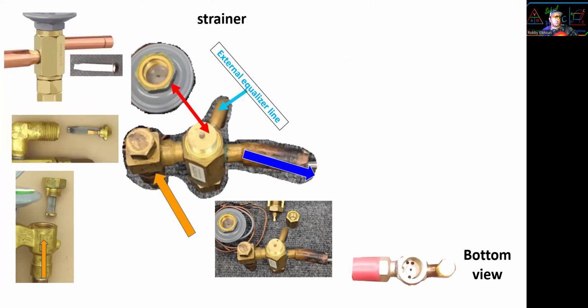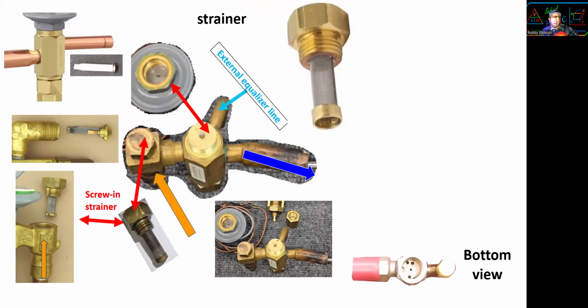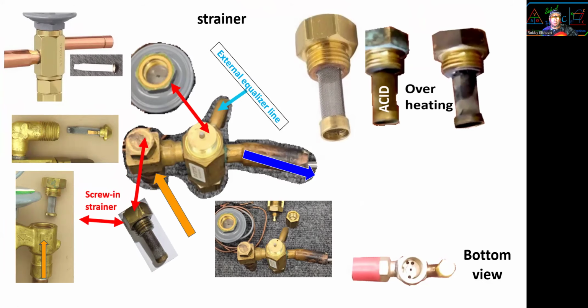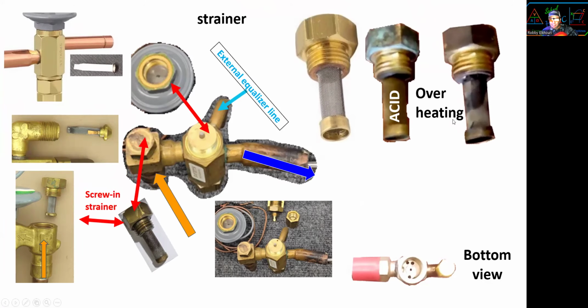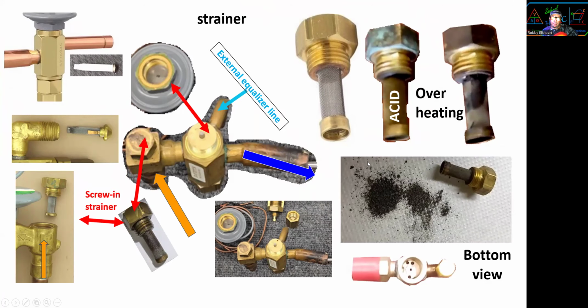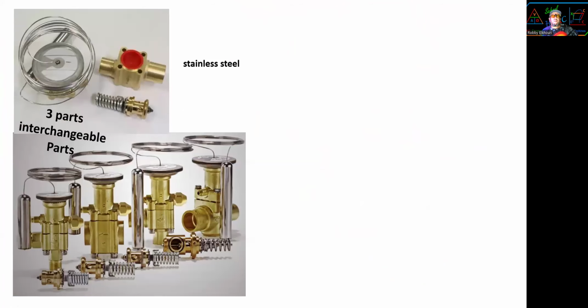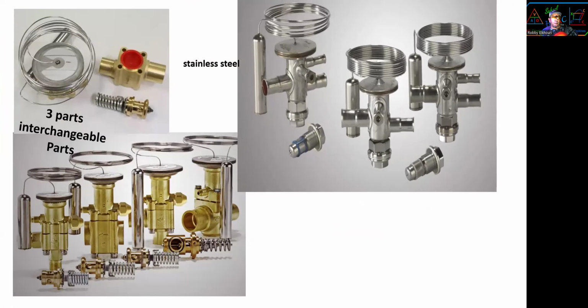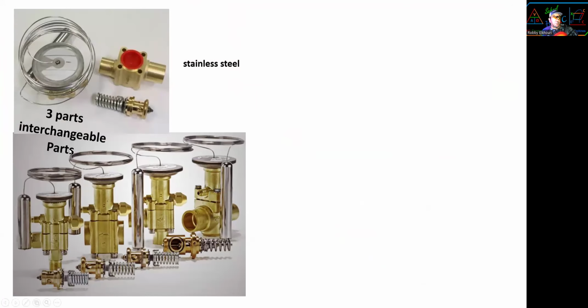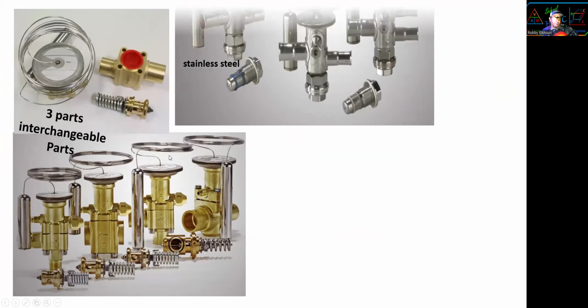Strainers, this is about strainers. There's this little filter that goes in the line. We have inline strainers, and we have screw-in type strainers. And that's the one brand new from the factory. And these overheated. One of them has acid, and here a little acid erosion. And there, how do you like that? This is going into the expansion valve, making it clog up. We have different kinds of expansion valves. These are stainless steel, three parts interchangeable. Look at that. You can, the body comes to the body, the head, and the spring.